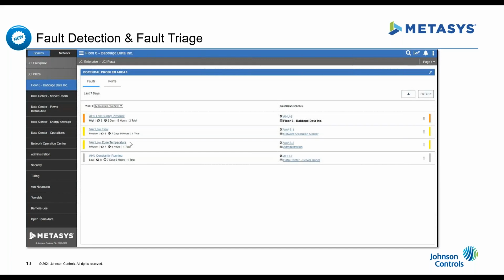I want to talk about fault detection first, and what a fault really is. When you think about alarms, we tend to alarm everything, and that often leads to nuisance alarms. With fault detection, we're able to eliminate a lot of those nuisance alarms.